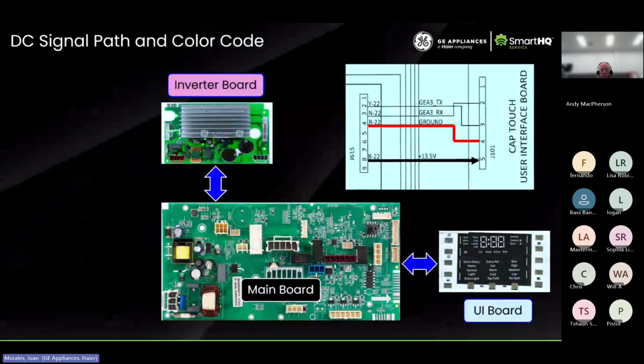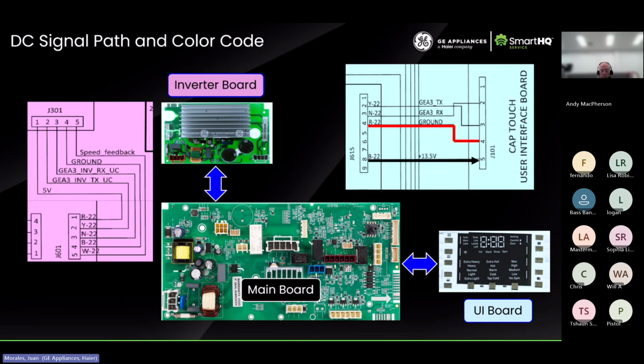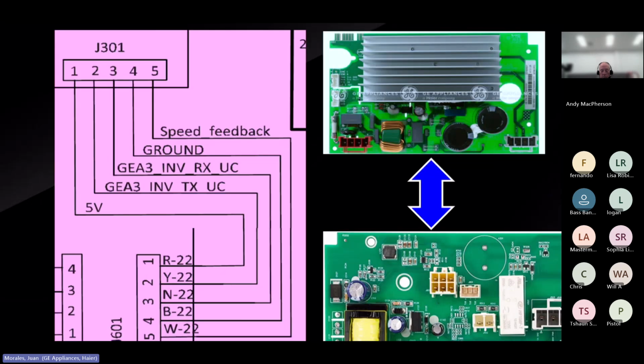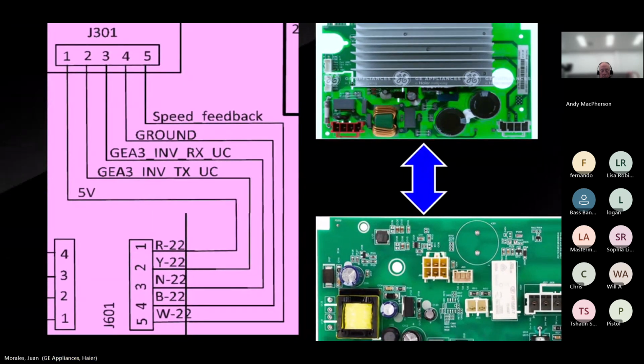So with that, we're going to switch over to the inverter board and take a look at the communication between the main and inverter. Let's zoom in here. We have 2 connectors: one at the main, J601, and one at the inverter, J301. The important cables we're concerned with, that we can actually measure with our meter, are the 5 volts on pin number 1.